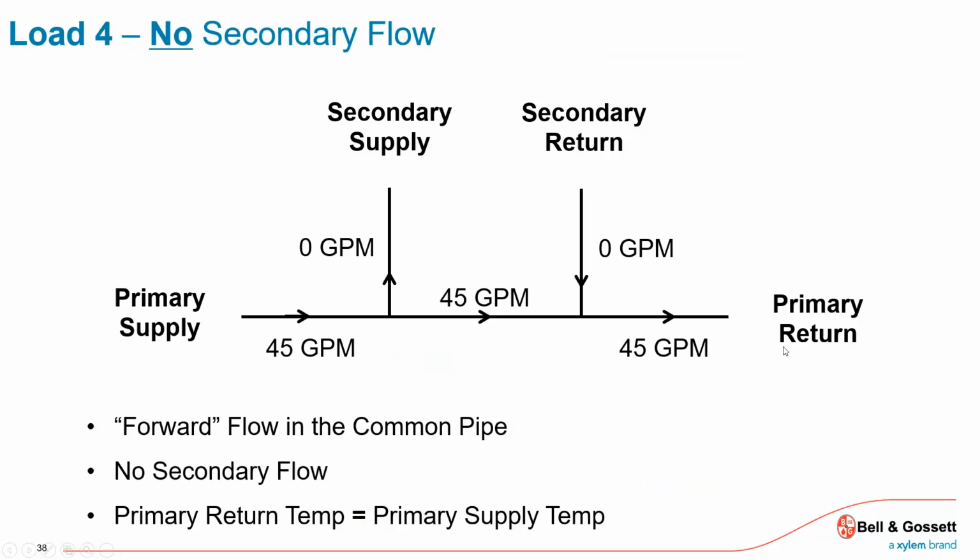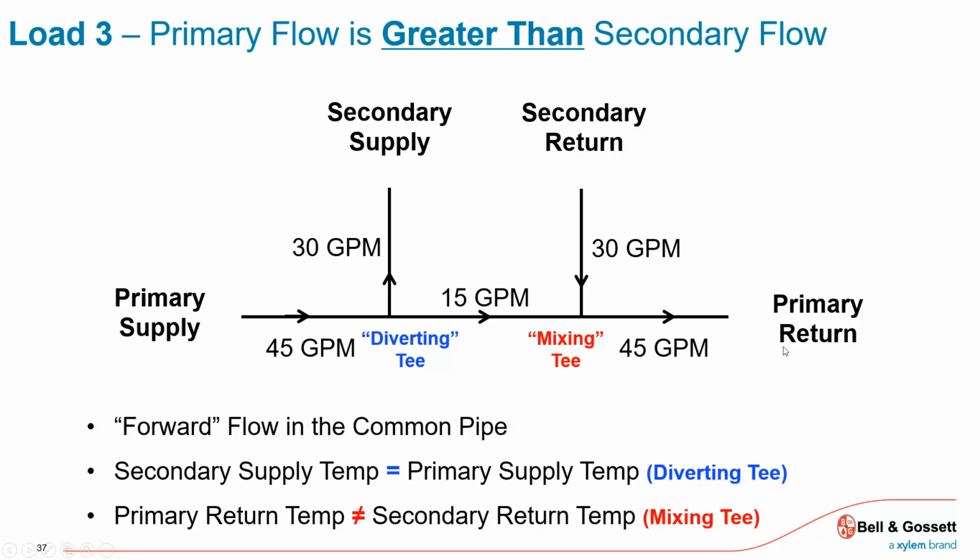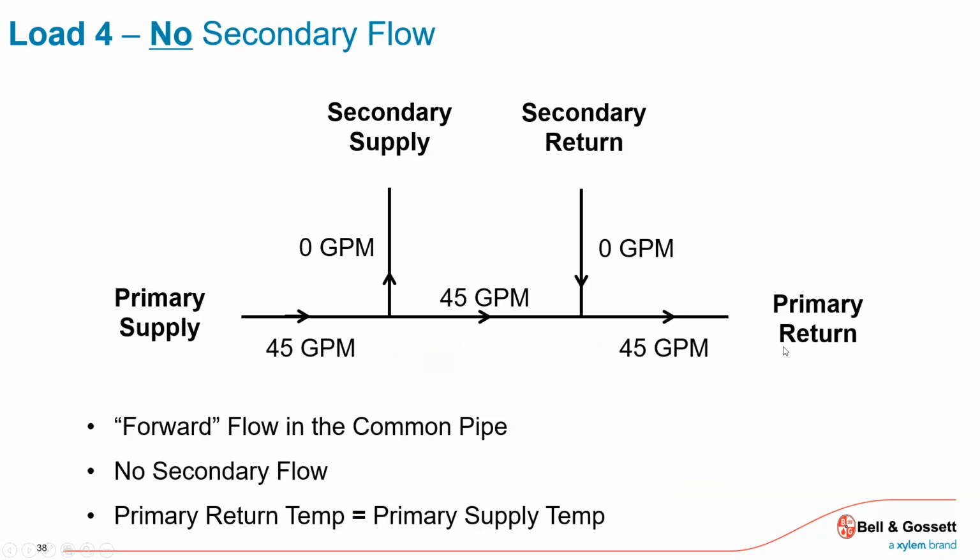On that example there, 45 gallons a minute, all of a sudden that pump, for whatever reason, the load is satisfied, that pump shuts off. That 15 gallons a minute immediately jumps to 45 in that circuit, in that one example. So those things are constantly occurring.